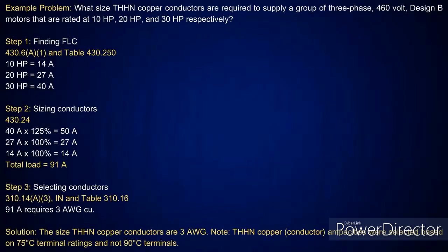Now, here's one where you've got multiple motors. Everything's still the same. I've got 460 volt 3-phase motors here. I've got a 10 horsepower, 20 horsepower, and 30 horsepower. Well, I already know the 30 is going to be the largest, but I go to table 430.250, get all my amperages. So a 10 horsepower is good for 14 amps, 20 horsepower is 27 amps, 30 horsepower is 40 amps. Then I go down to step 2, and if I look at 430.24, the largest motor is taken at 125%. All the rest are taken at 100%. So 40 amps times 125% is 50 amps. Then add the 27 amp and the 14 amp motors, and that gives you 91 amps. Go to table 310.16. The next size above that, in the 75-degree C column, is 100 amps, which requires a number 3 conductor. Now, was that hard?